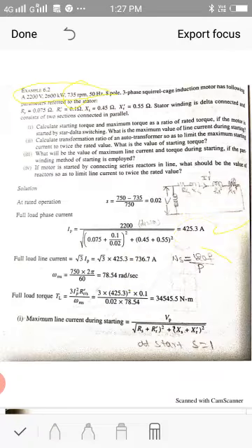Okay, so here I have this much. I am going to substitute everything here. ip is the phase current. Okay, so it is 425.3. rr is given here. Okay, rr is 0.1, and omega ms is 78.54, and this slip s is 0.02, because I am calculating the full load torque. Okay, at full load torque the slip will be equal to 0.02, that we have calculated here.